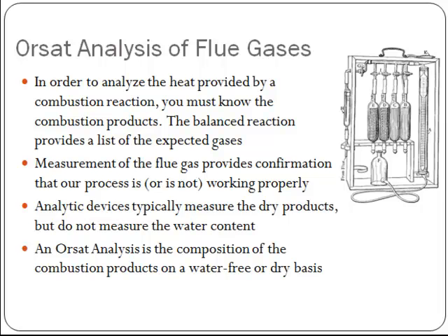So to measure that, the device that was first developed is an Orsat analyzer, and variations of this are still used today. But an Orsat analyzer, old school form, you would bring in a bottle of your flue gas, you'd capture it in a bottle, and then you would allow it to pass through some various kinds of absorption columns, okay?